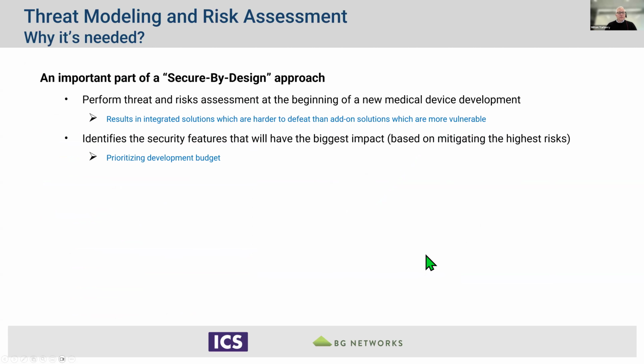Why is threat modeling and risk assessment needed? One of the first arguments I'd reach for is that it's an important part of the secure by design approach, and this is something you want to do at the beginning of a new medical device development. The result is you get integrated solutions, which are harder to defeat in your product than solutions which are more tacked on. Those are going to be more vulnerable. It also identifies features that will have the biggest impact, and you can use that in figuring out where you put your effort, where you put your budget, that sort of thing.